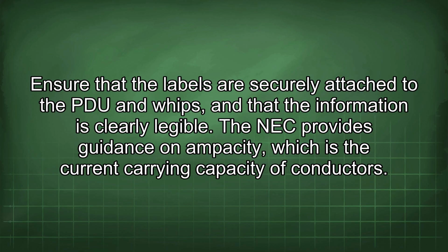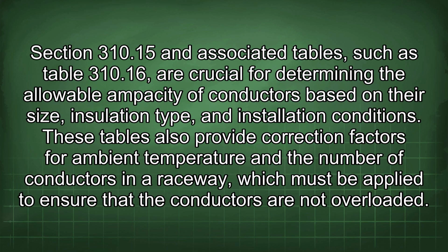The NEC provides guidance on ampacity, which is the current carrying capacity of conductors. Section 310.15 and associated tables, such as Table 310.16, are crucial for determining the allowable ampacity of conductors based on their size, insulation type, and installation conditions. These tables also provide correction factors for ambient temperature and the number of conductors in a raceway, which must be applied to ensure that the conductors are not overloaded.